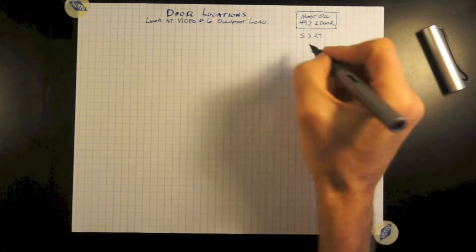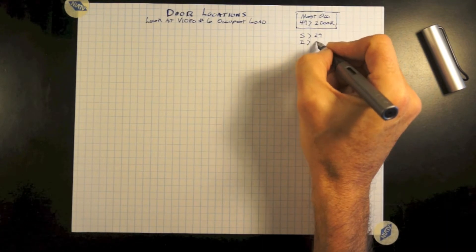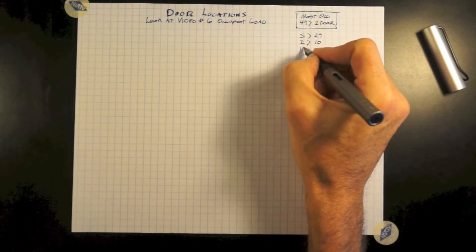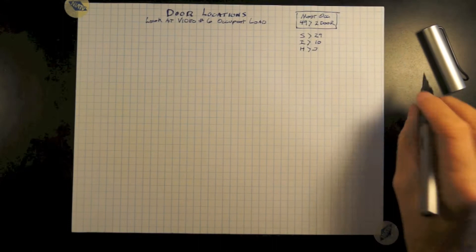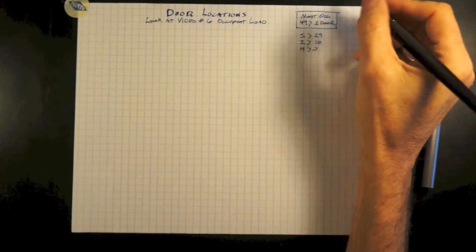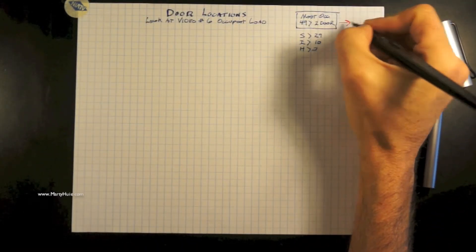For storage, it's 29. For most I occupancies, it's around 10. And for H hazard, it is three persons will require more than one door exiting the space.